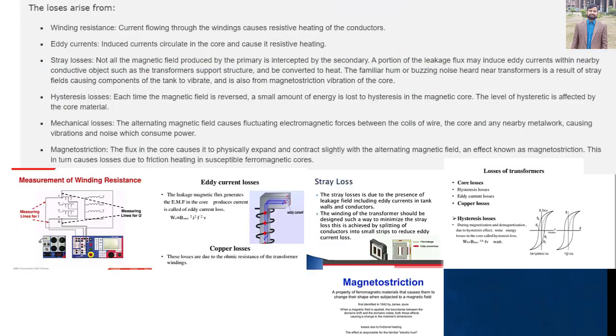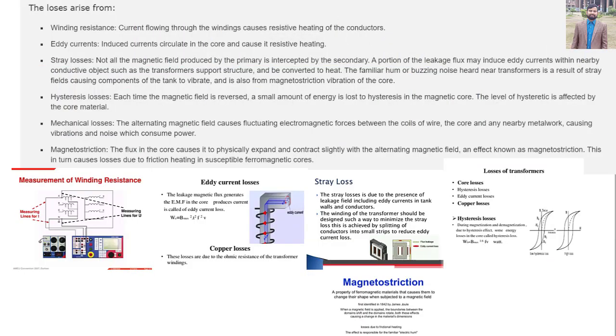The losses arise from winding resistance. Current flowing through the windings causes resistive heating of the conductors. Eddy currents: induced currents circulate in the core and cause resistive heating. Stray losses: not all the magnetic field produced by the primary is intercepted by the secondary.